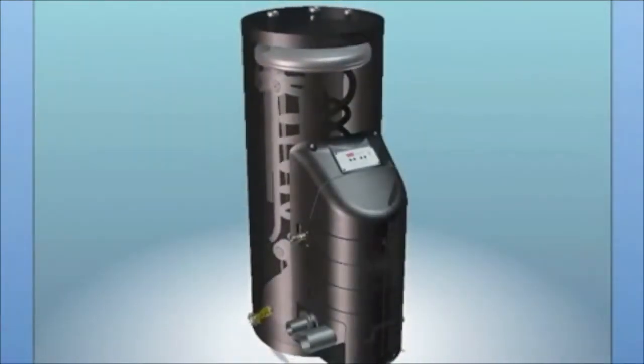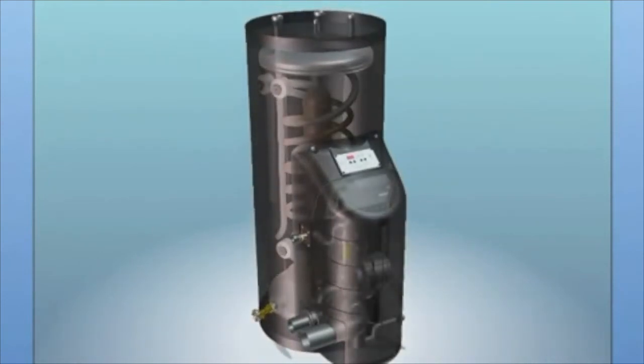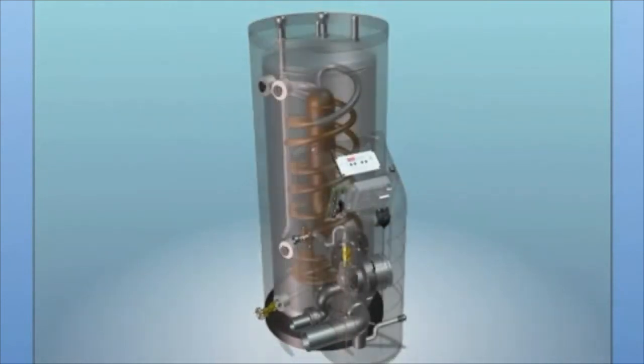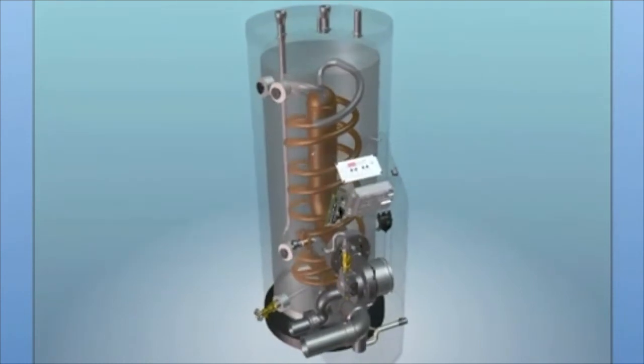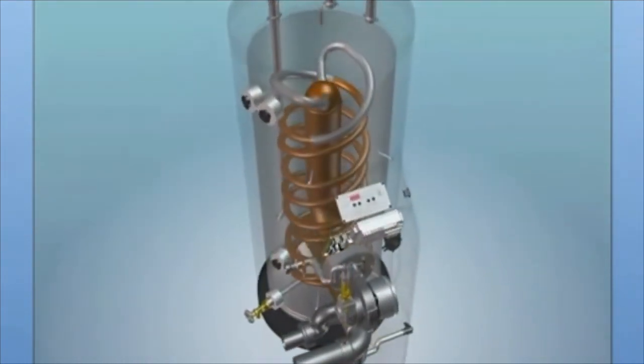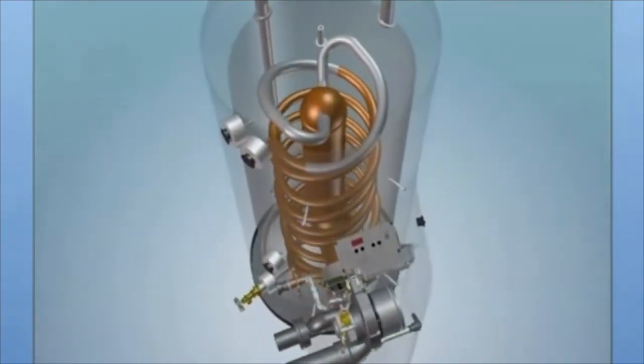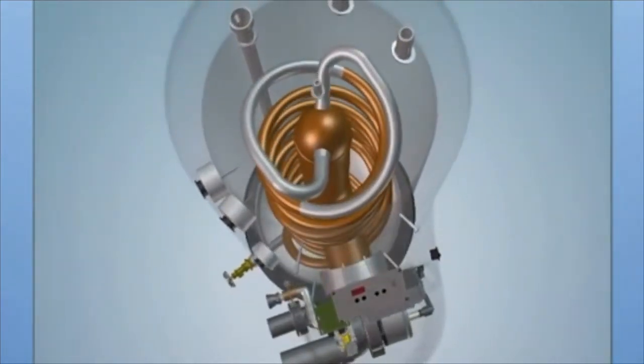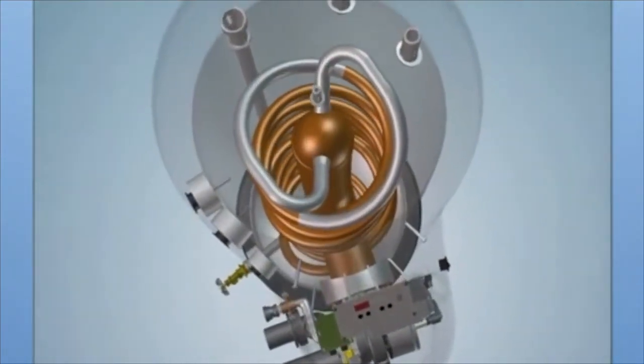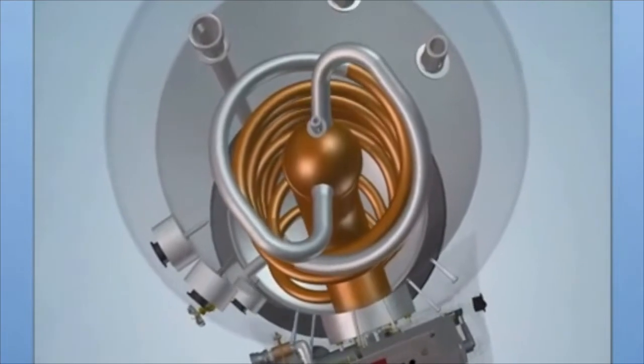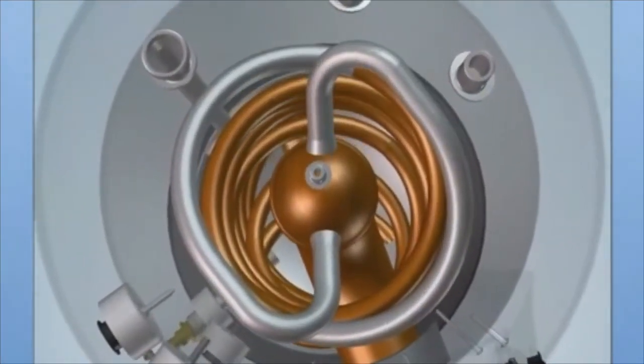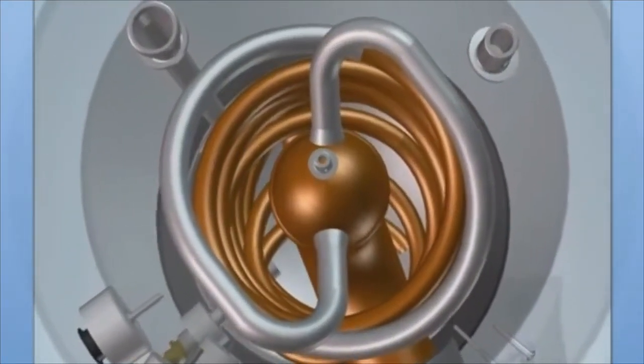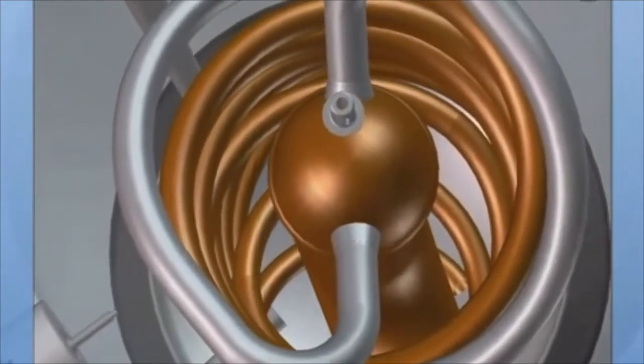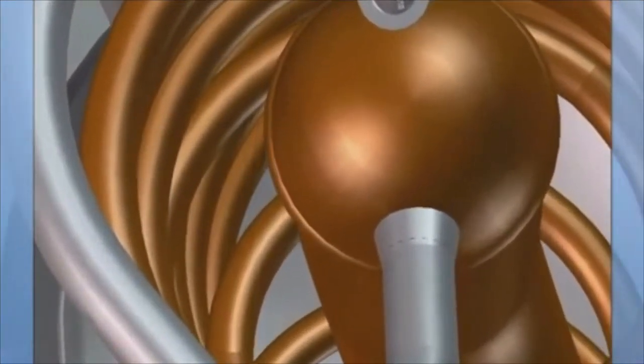HTP's proprietary heat exchanger design. The major advantage of condensing technology is to extract more heat from the exhaust gas compared to conventional systems. The heat exchanger incorporates a larger surface area constructed of high-quality 90/10 cupronickel, which allows the unit to extract all of the latent energy from the water vapor contained within the exhaust gas. This reclamation of energy allows the appliance to use less energy to meet desired heating loads.